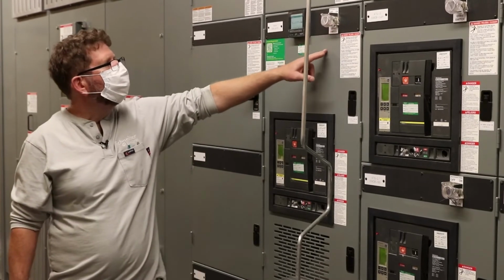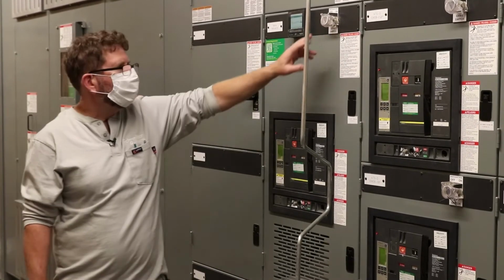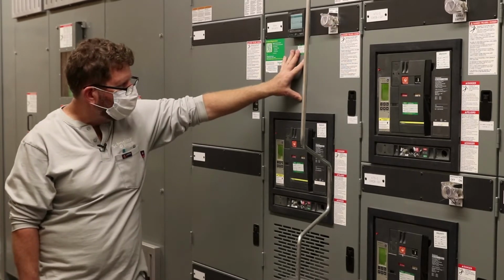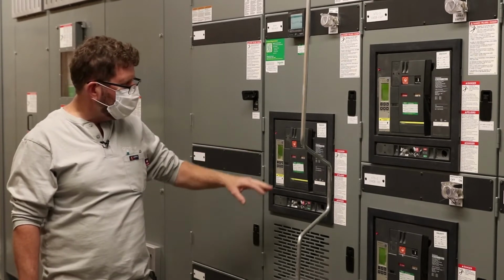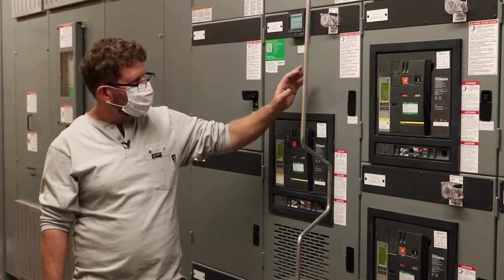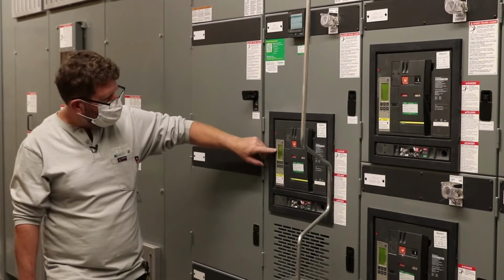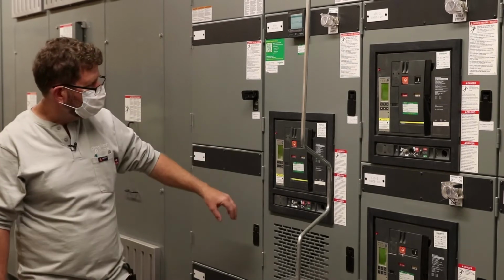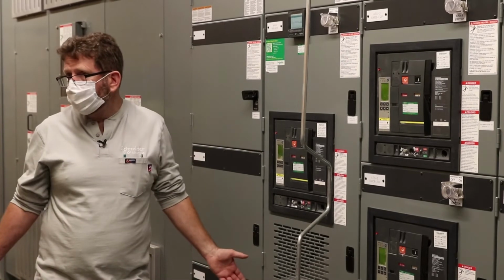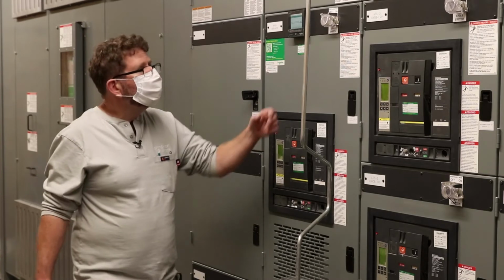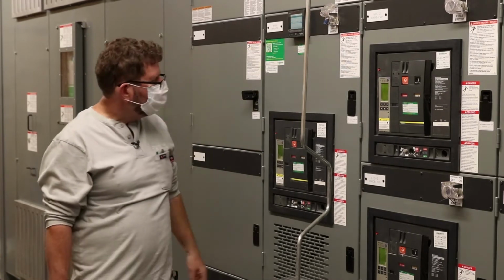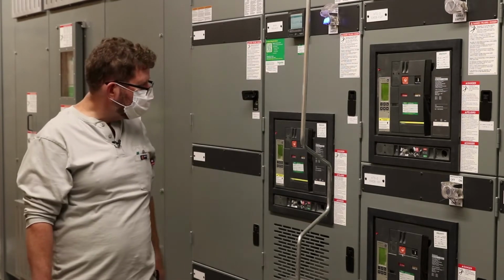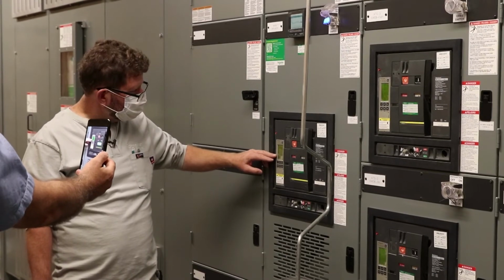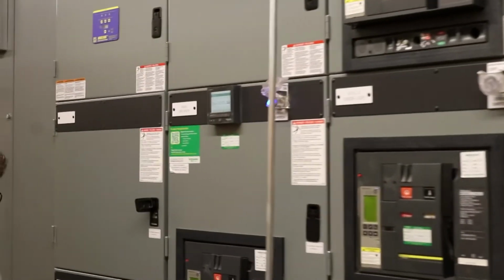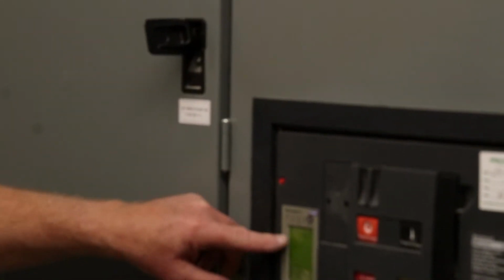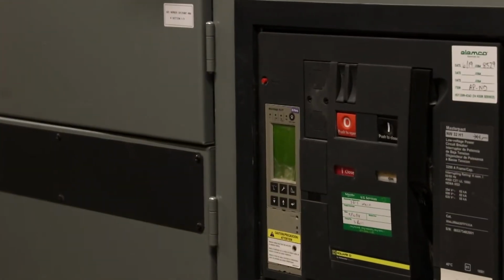When you turn the ERMS switch to on, this light will come on blue. It closes the contact, which goes into an input-output module, which will then tell the breaker to go into ERMS mode. When the breaker goes into ERMS mode, it'll light this light up blue. It'll also, across here, flash ERMS. You'll see an hourglass shape and then ERMS. We can do it now if you want, and there's really no risk to it. Hourglass, you're in ERMS mode, and when you get here, it's going to flash periodically ERMS and then go back to normal.